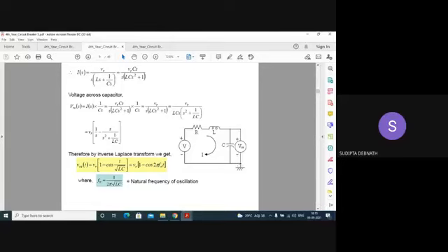Now, after final arc extinction at current zero, the voltage across the contacts of a circuit breaker is composed of power frequency and high frequency transient components. Okay. The transient frequency component has a very high frequency and dies out rapidly after final arc extinction. And recovery voltage is the power frequency RMS voltage which appears across the contacts after final arc extinction.